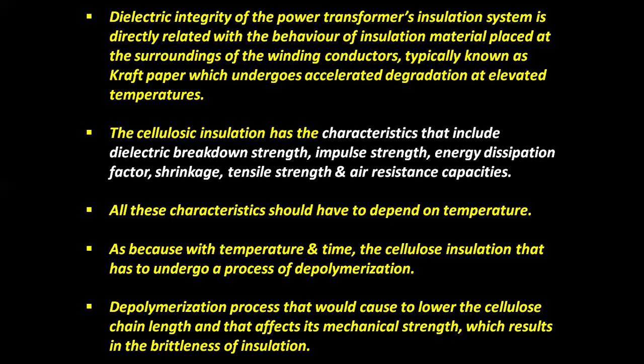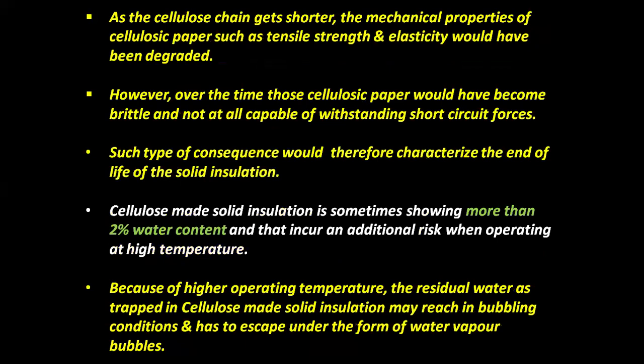temperature. Because with temperature and time, the cellulose insulation undergoes a process of depolymerization, which lowers the cellulose chain length and affects its mechanical strength, which results in brittleness of the insulation. As the cellulose chain gets shorter, the mechanical properties of cellulosic paper, such as tensile strength and elasticity, are degraded. Over time, the cellulosic paper becomes brittle and not at all capable of withstanding short circuit forces. Such a consequence would characterize the end of life of the solid insulation.